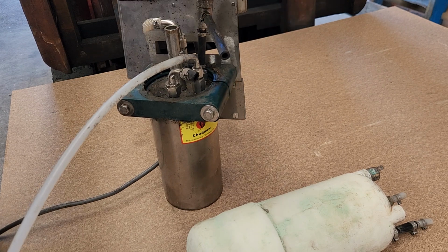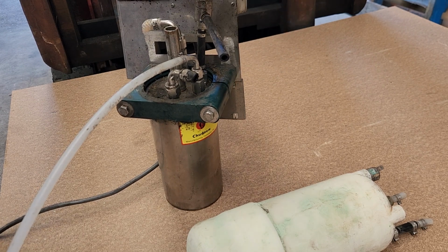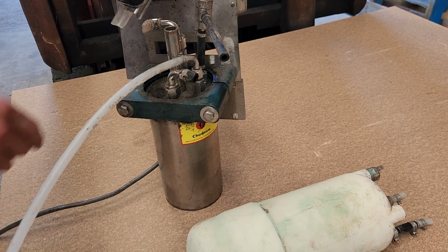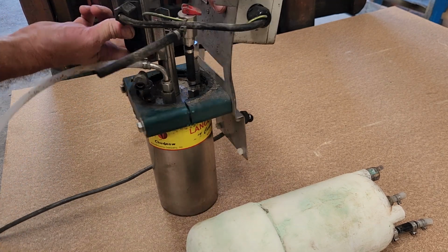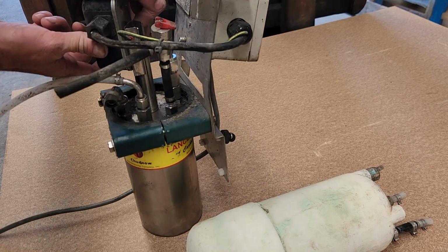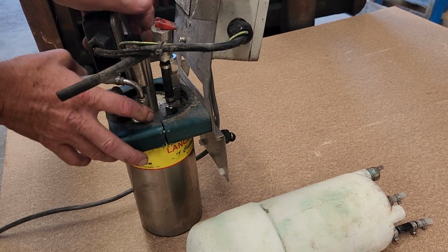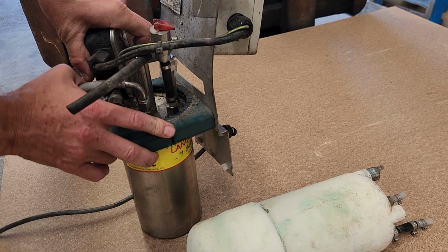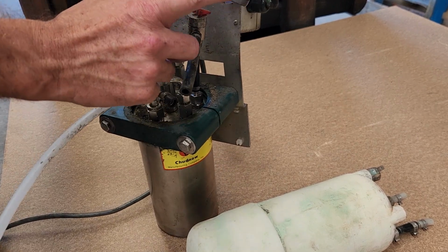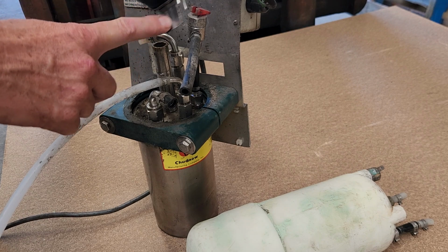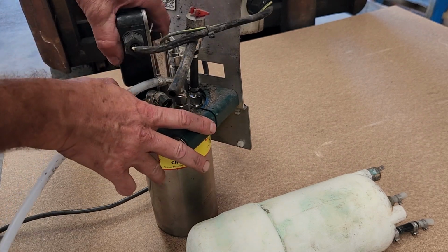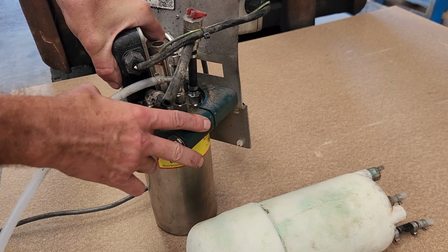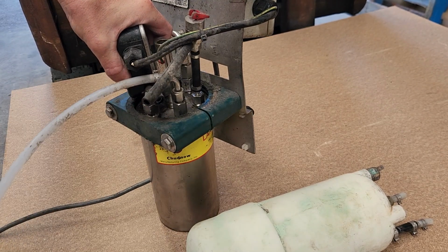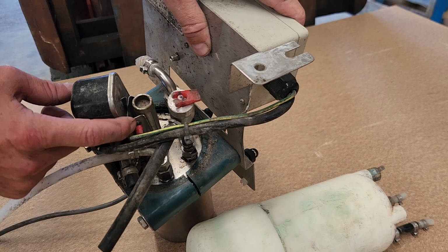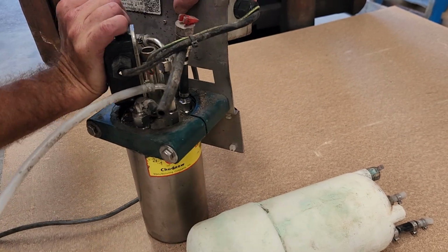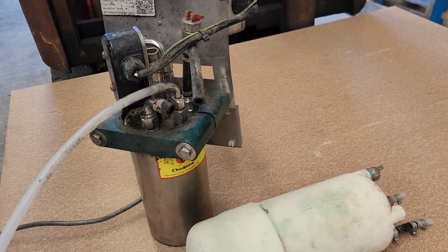Now, this also has to be placed fairly precisely on the spindle. So what you need is to make sure it's clipped on properly, then pushed all the way to the bottom. If it's not all the way to the bottom, if it's hitting something, then there's an issue. Usually you'll find one of these on the bottom. That is a measurement from the bottom. So it measures how far it should be pushed down, all the way down, till it's solidly against the bottom, and if it comes away from that, it's also going to be a problem, so then it needs to be pushed in and up tight.